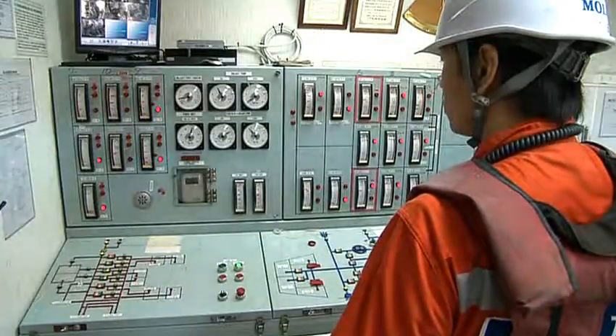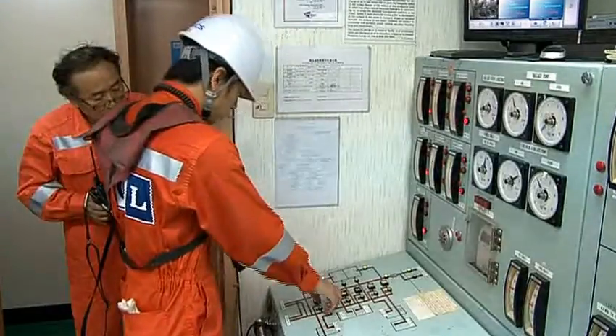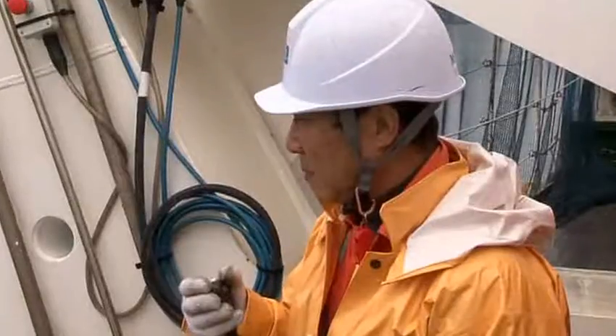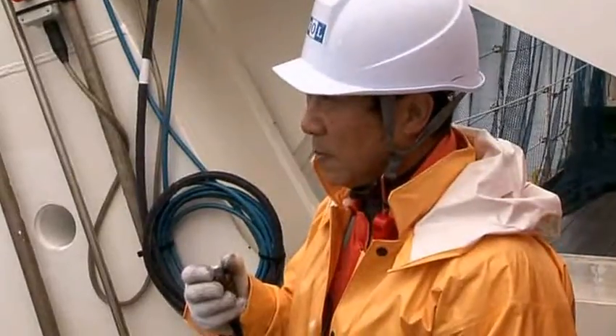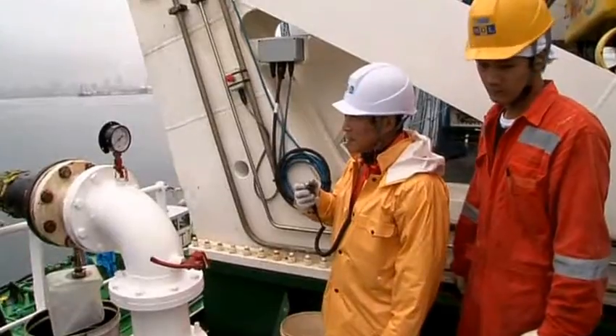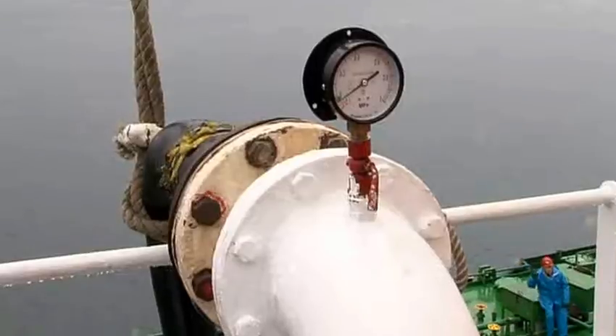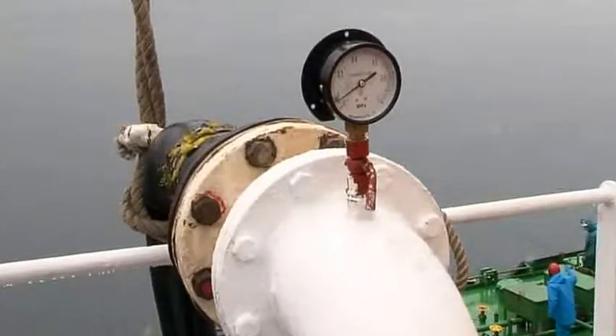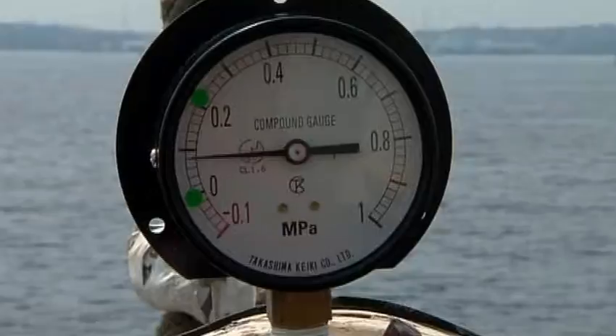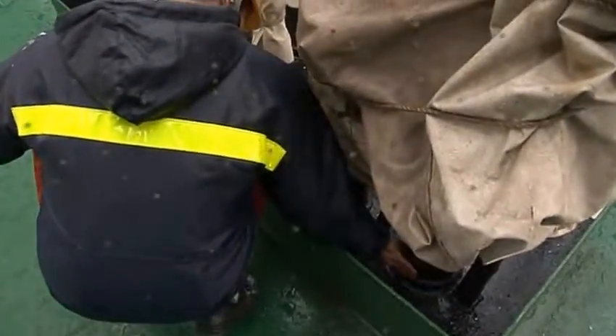During the bunkering operation, always remember to maintain close communication between the control room and the operation site. Also remember to post a watchman at the bunkering manifold. Never leave the bunker manifold and sounding pipes unattended. If there is no problem, raise the oil transfer rate to the prescribed rate. Keep watch on bunkering operations at all times, including on the opposite side of the bunkering station.